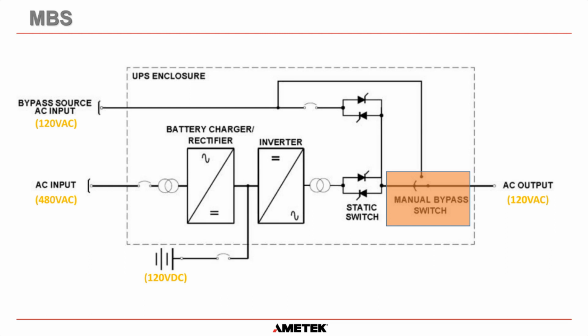But please remember one thing. A manual bypass switch and a static switch are two completely different components. They have no relationship to each other. In other words, what I mean by that is the manual bypass switch has no interaction with the static switch, and the static switch has no automatic interaction with the manual bypass switch. Okay, they are two separate things. They should be considered two separate things, and I'll explain why in just a moment.